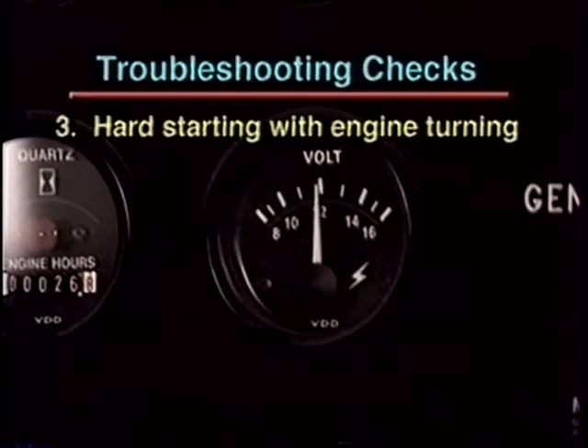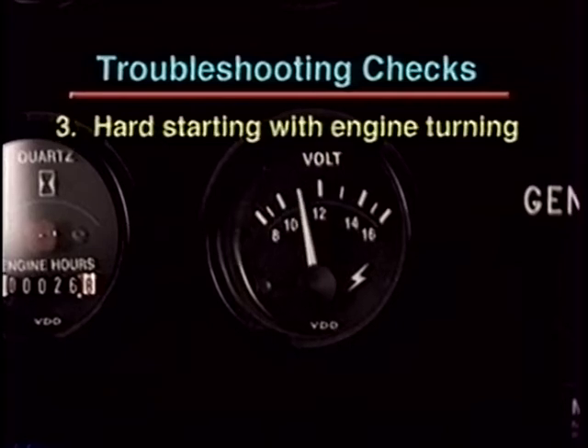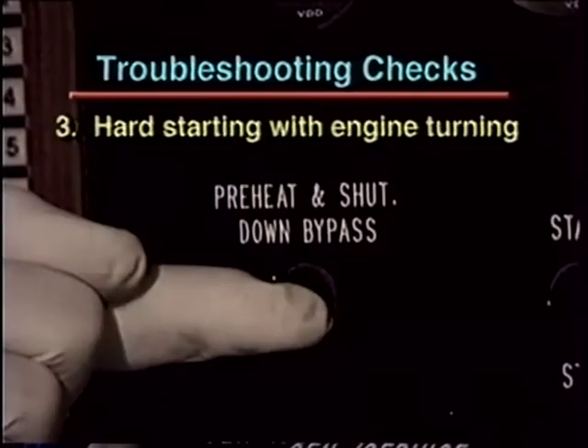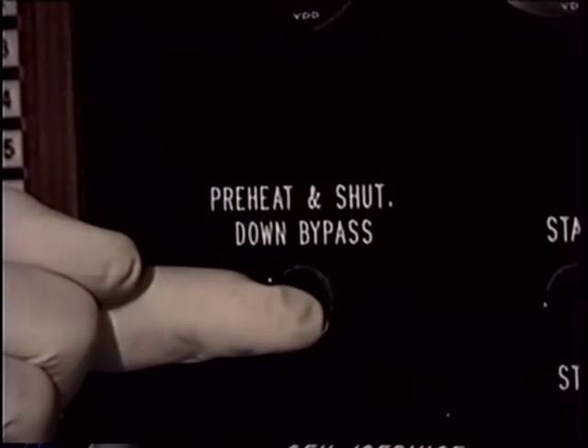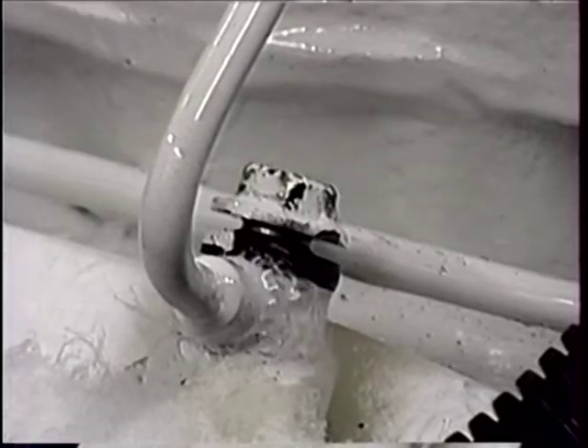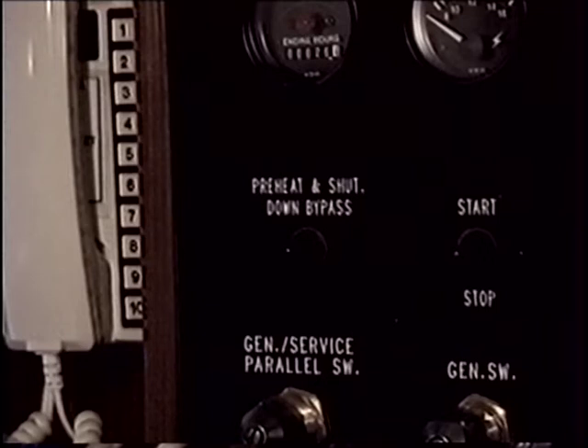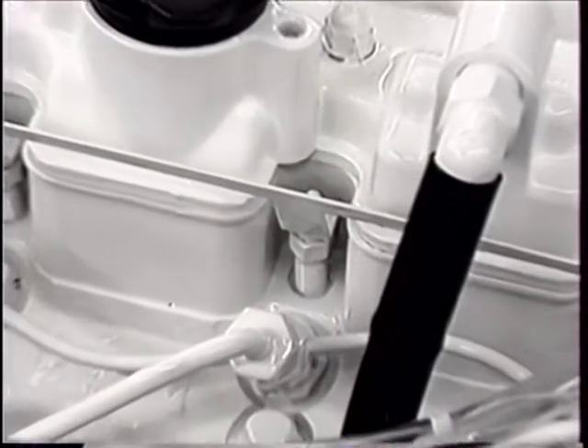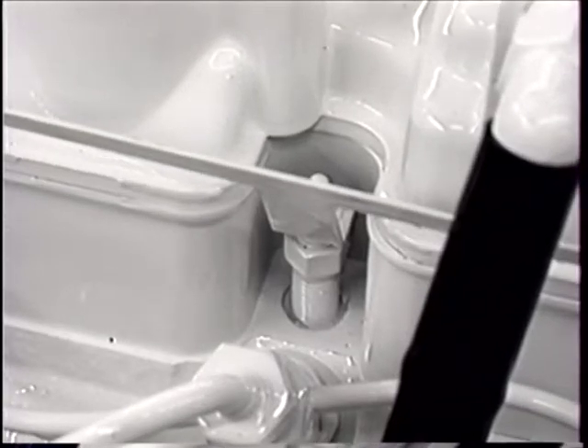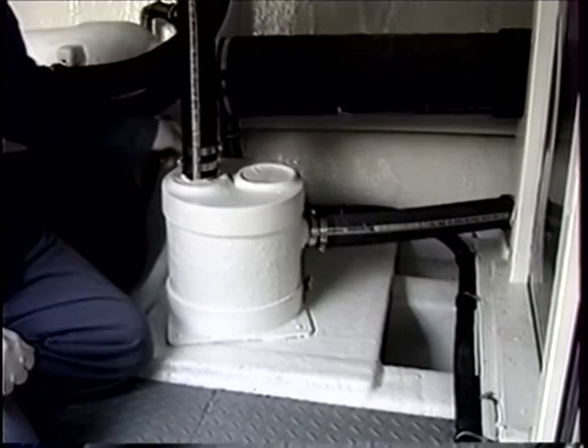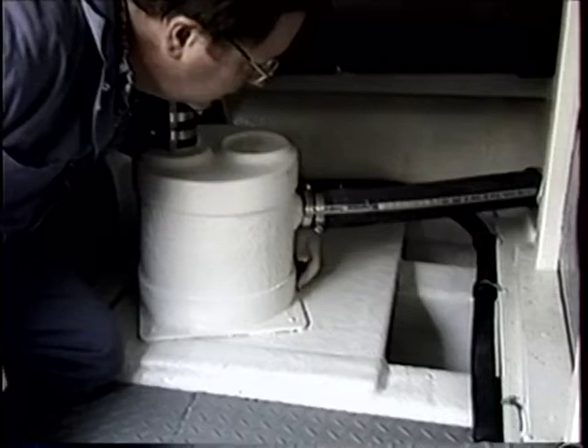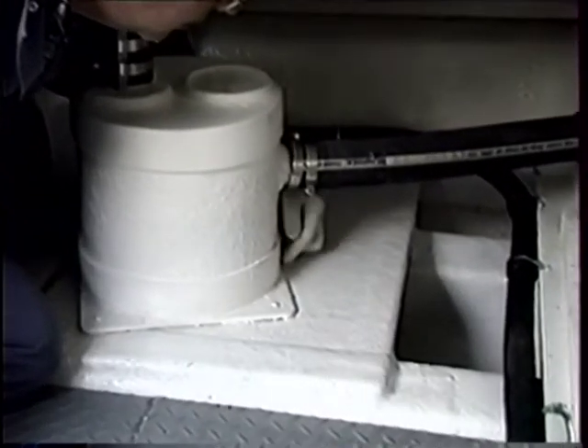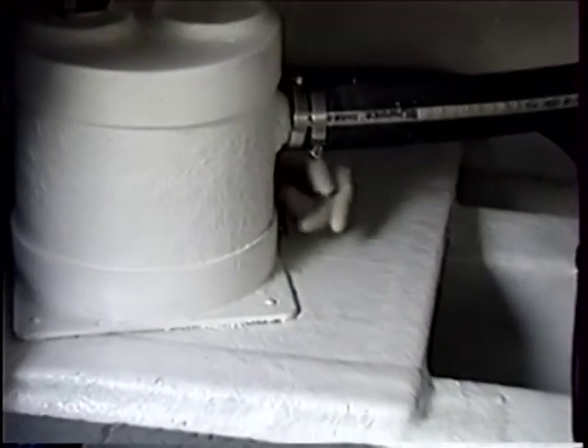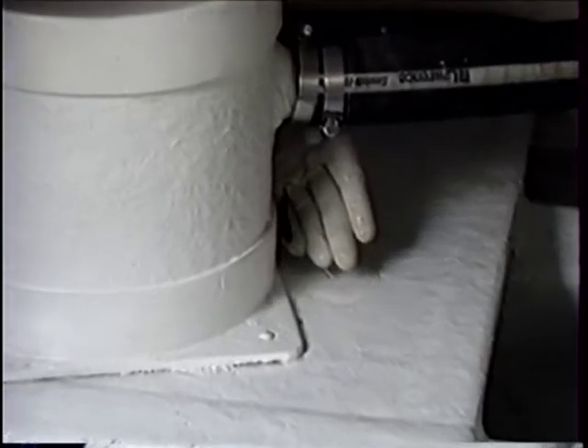Problems of hard starting with the engine turning over can be caused by low battery voltage, incorrect use of the bypass preheat switch, restricted fuel supply, air in the fuel line, failure to arm the fuel system by activating the solenoid, or a failed preheater circuit. Note that excessive cranking can cause the exhaust to fill with water, back up and run directly into the engine. Drain the muffler if necessary to prevent this.